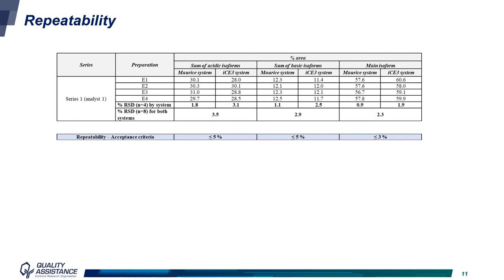Moving on to the first results, this table has three main columns with percentage area for acidic, basic, and main variants. For each column, data is divided between the Maurice system and iCE3 system. Samples in this series were prepared four times individually and injected on both systems. Acceptance criteria of 5% were set for repeatability on the acidic and basic charge variants, and lower than 3% for the main variant. Looking at each system individually, the error is lower than the acceptance criteria, and even the error of the combined data for both systems is lower than the criteria, indicating comparable data on both systems.